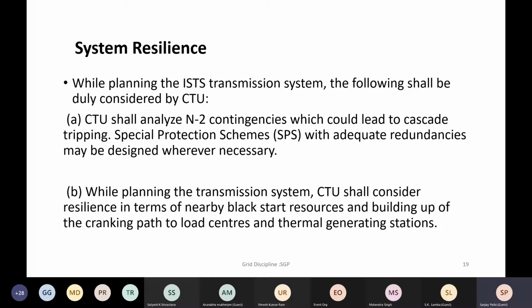We talk about system resilience, so we talked about the special protection scheme. This is actually the wording of the technical provision in the grid code, where CTU shall analyze N-2 contingencies which could lead to cascade tripping. The cascade tripping, which was a very regular phenomenon at one point of time, has over a period of time been minimized with various protection schemes as well as the special protection scheme. Along with this, there is also a provision to have controlled isolation of the regions and areas, including black start provisions from certain power stations to restore the supply after certain areas face complete shutdown.